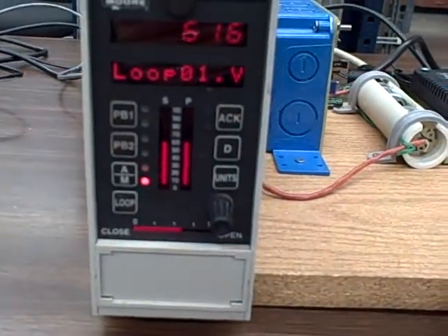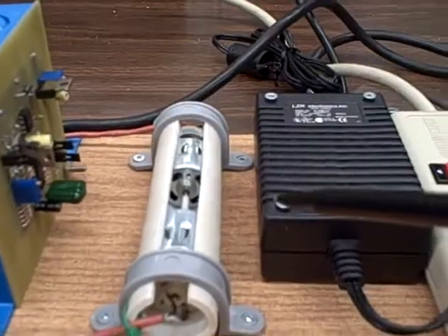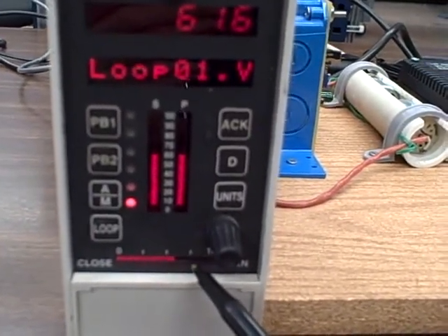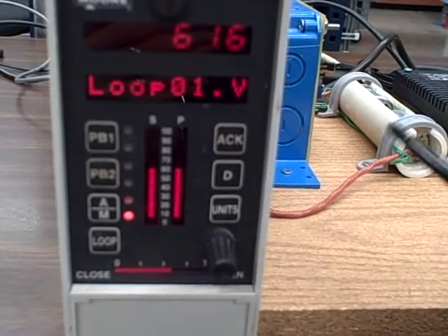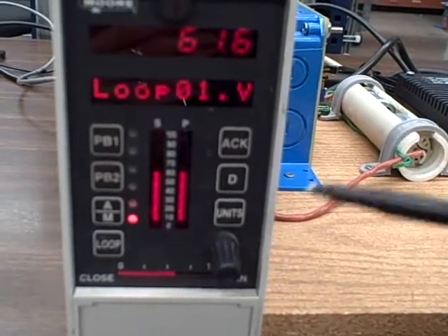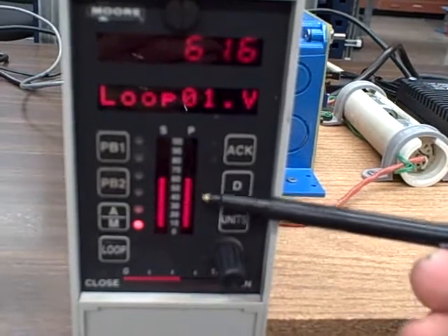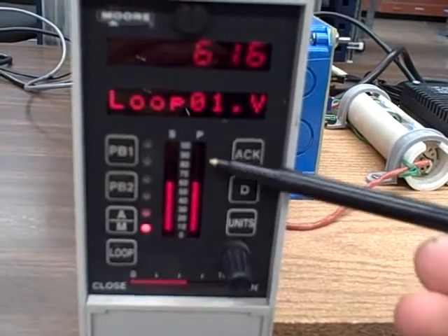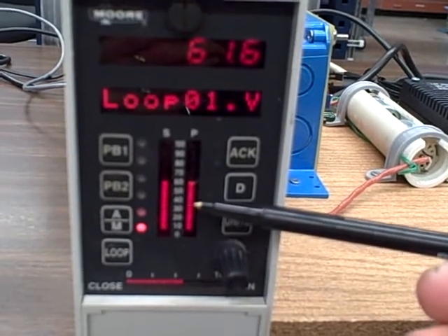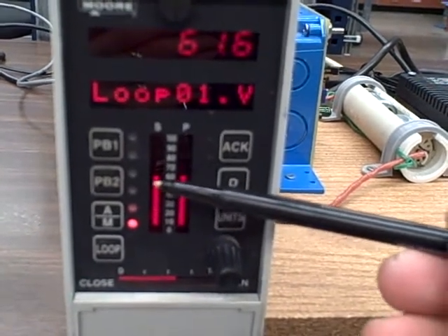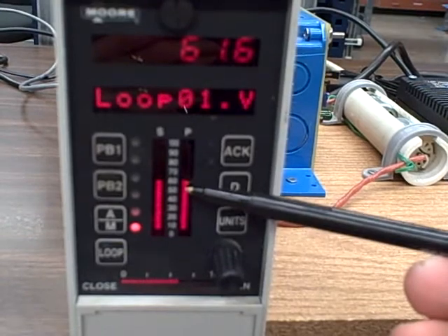The motor is now spinning faster. You can actually hear it spin faster. That's because I've driven a stronger 4 to 20 milliamp current at the output of the controller. In response to that, the generator notes that the motor is spinning faster and sends a stronger voltage signal back, which gets read out as our process variable, or P. Because the controller is in manual mode and it has the set point tracking feature enabled, it automatically sets the set point equal to the process variable.